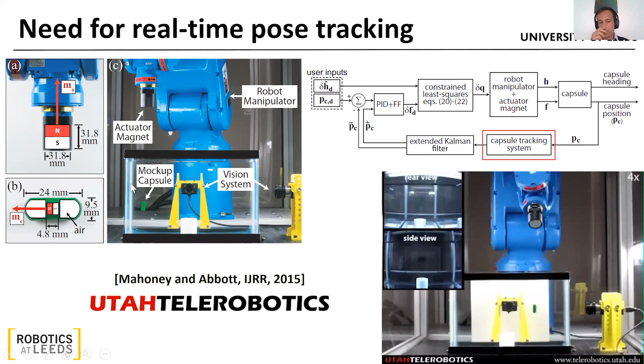So, we developed our own real-time pose detection strategy by integrating 1 accelerometer and 3 couples of Hall effect sensors inside the tip of the magnetic endoscope. The Hall effect sensors are aligned along the 3 main Cartesian axes and placed around the internal magnet. Once the offset due to the internal magnet is removed, the Hall effect sensors provide the reading of the magnetic field vector generated by the external magnet at the tip of the magnetic endoscope.